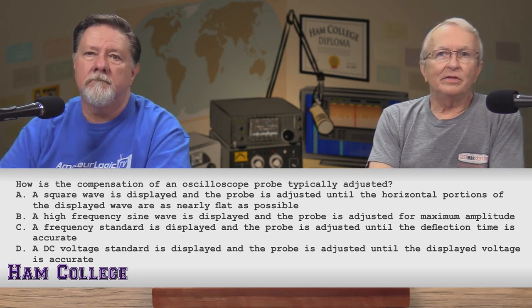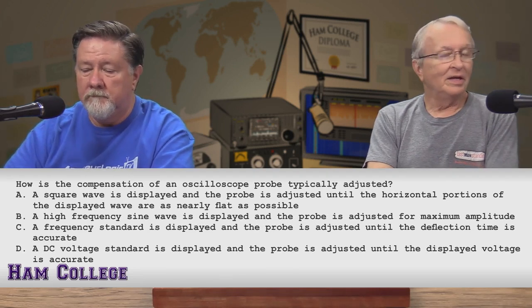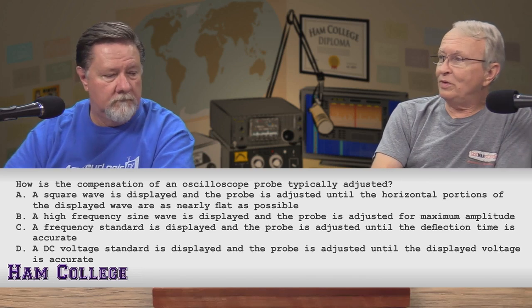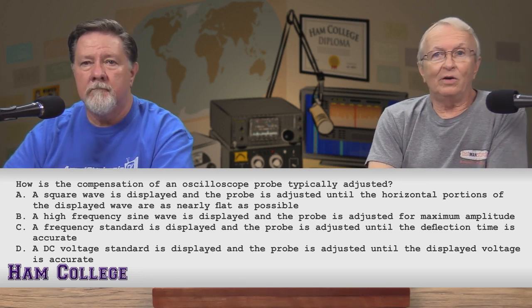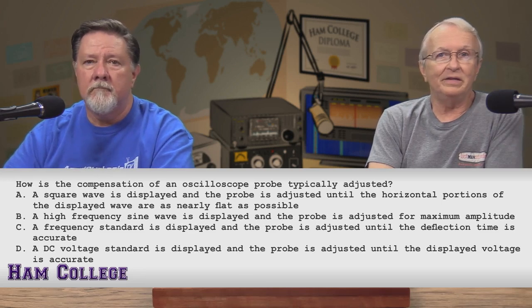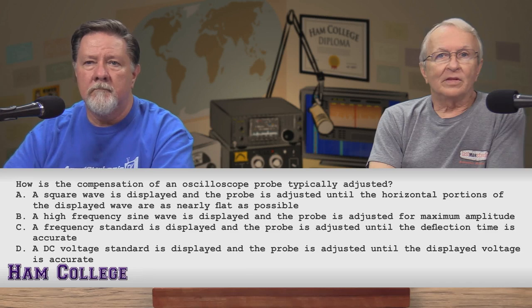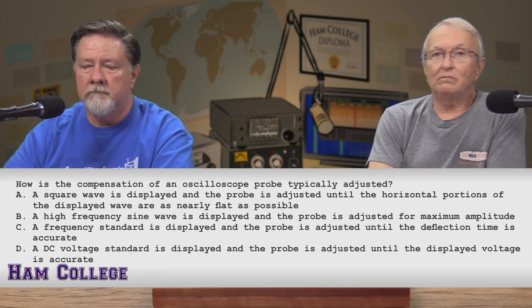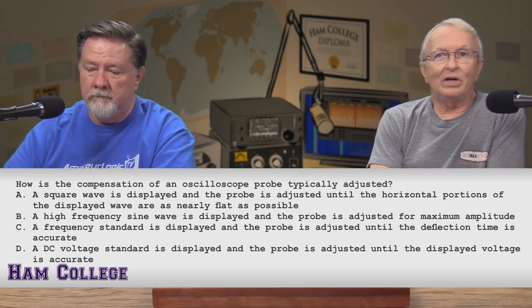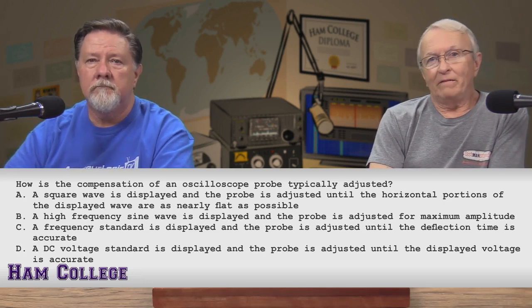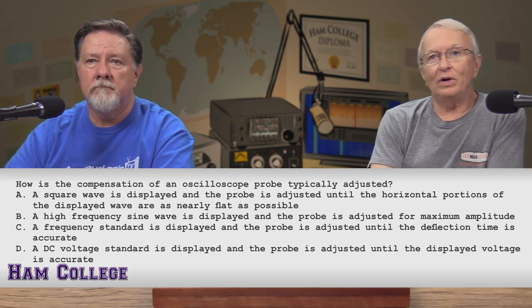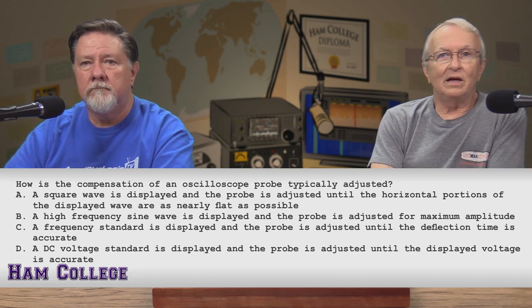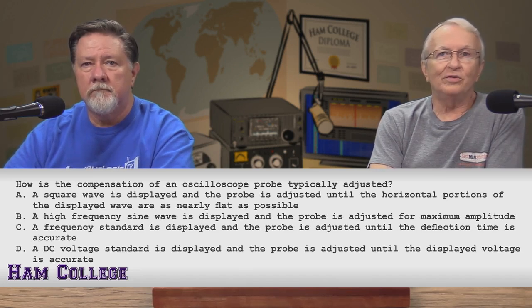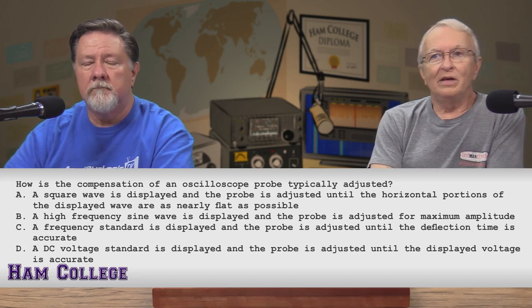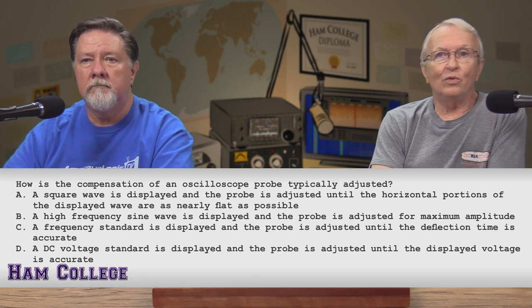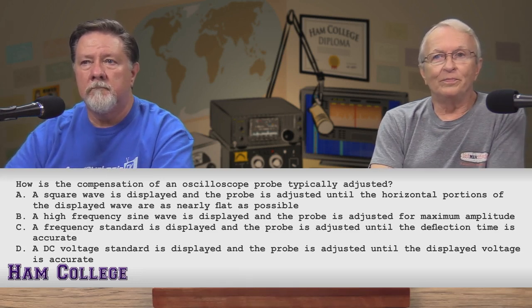How is the compensation of an oscilloscope probe typically adjusted? This is one of those things I was thinking we'd look at tonight. It's not a DC voltage you're trying to adjust, so it's not D. C, a frequency standard is displayed, no. B, a high frequency sine wave is displayed, no. Typically it's a low frequency signal and a square wave you're looking at. So I'm saying it's A, a square wave is displayed and the probe is adjusted until the horizontal portions of the displayed wave are as nearly flat as possible.